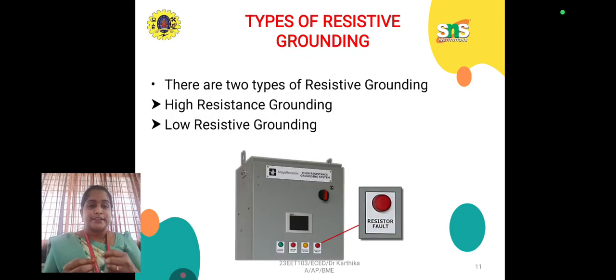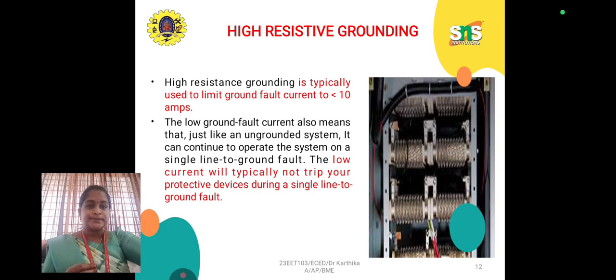See, types of resistive grounding. We have high resistance grounding and low resistance grounding. See the diagram, which is our practical high and low resistive grounding systems. See the high resistive grounding. It is typically used to limit the ground fault current to between 0 and less than 10 amps.